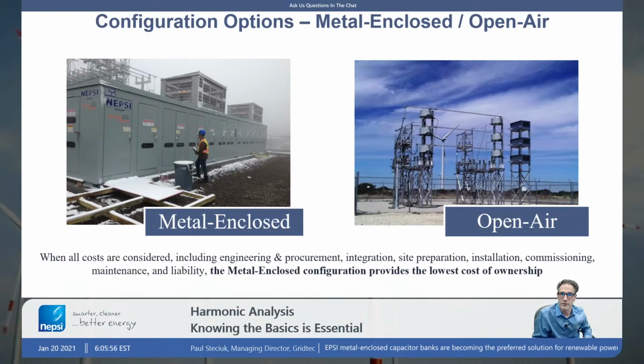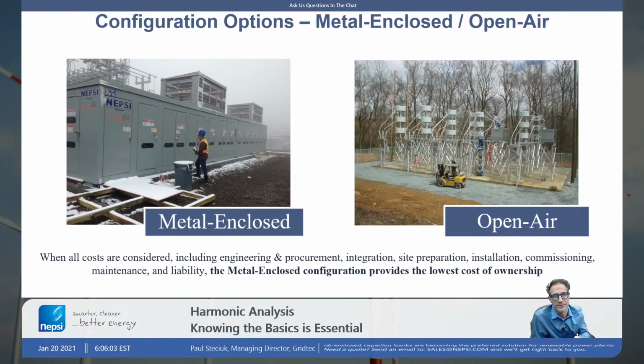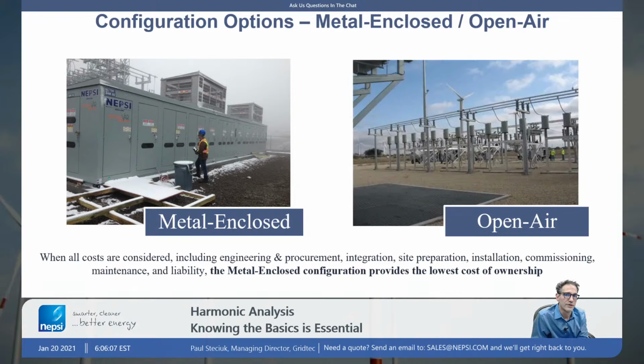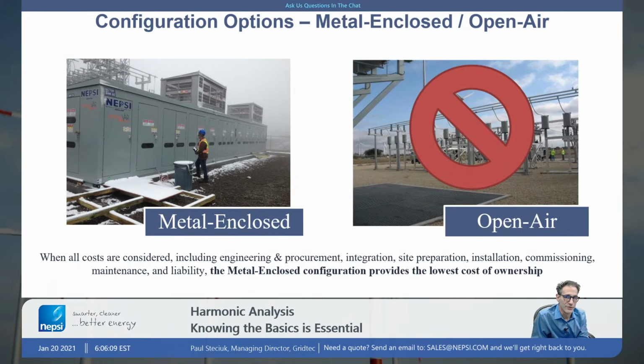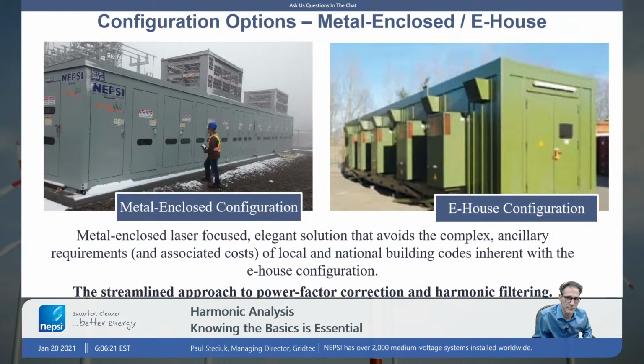Maybe before we move on for these two first. So metal-enclosed solutions on the left, open air is on the right. And we can see that there's different configurations, but the end result is NEPSI does not produce open air solutions. They take up a lot of space. It's not an integrated solution. It's a more complex solution. It's more difficult to install in the substation, and it takes a lot of area. So metal-enclosed solution is what we provide.